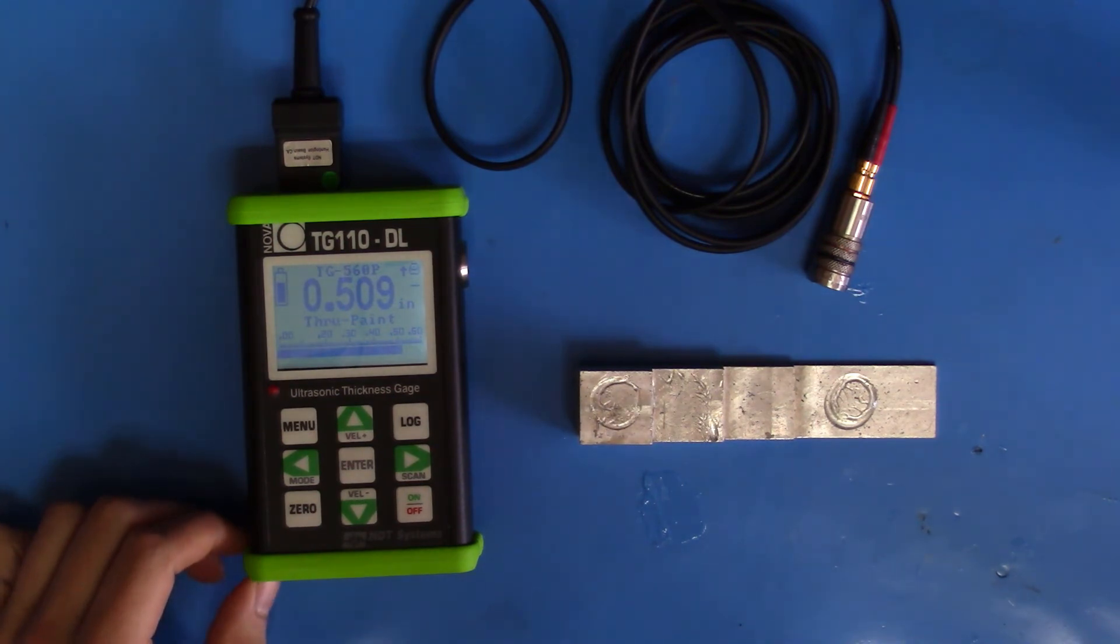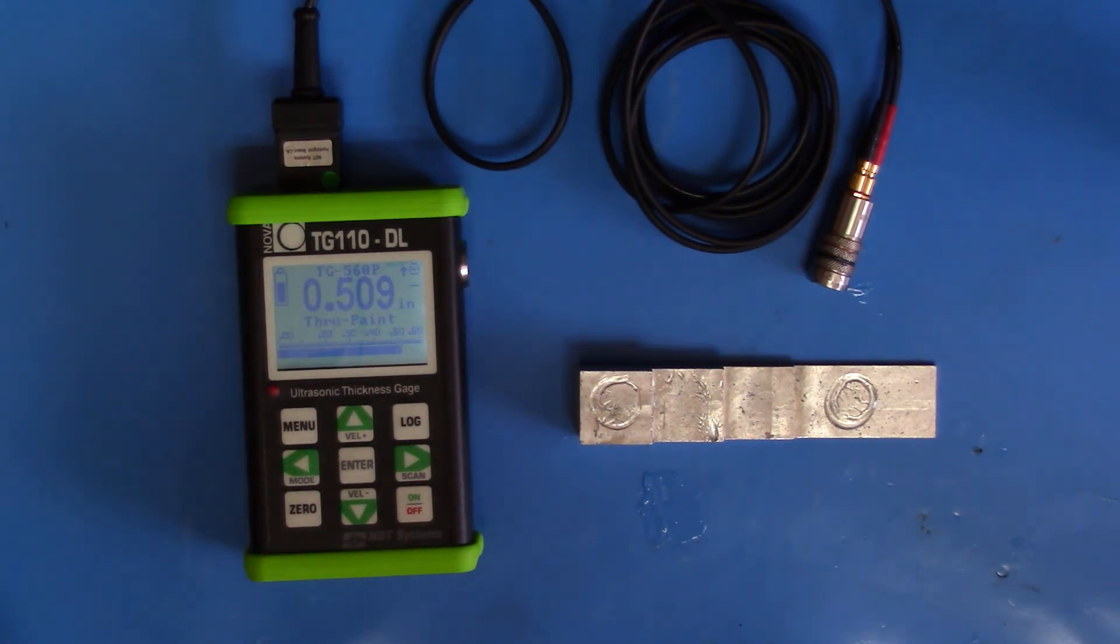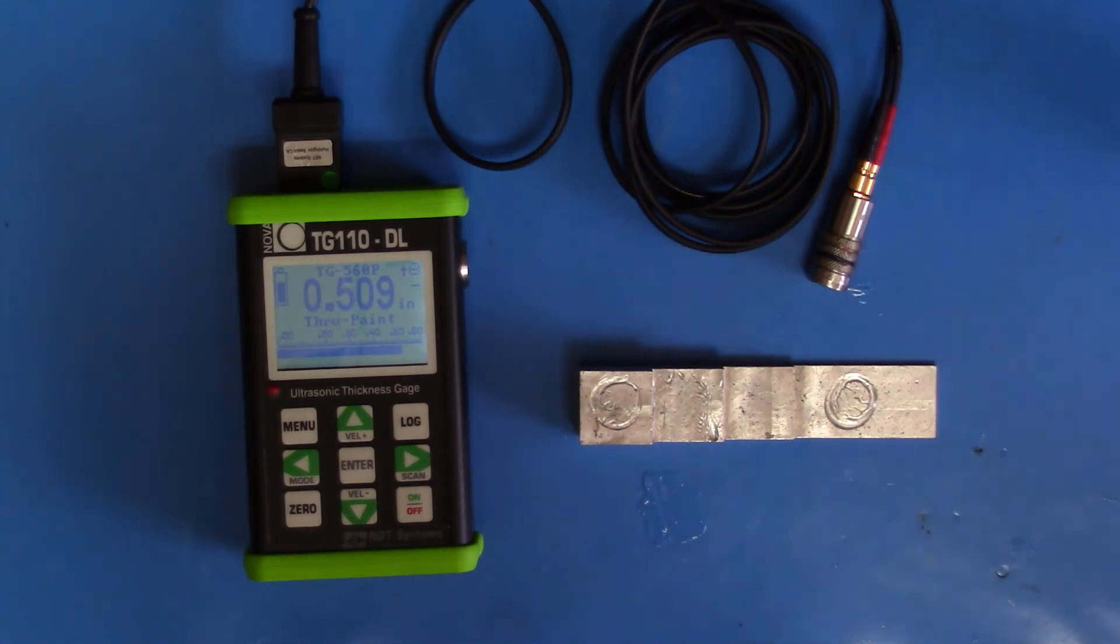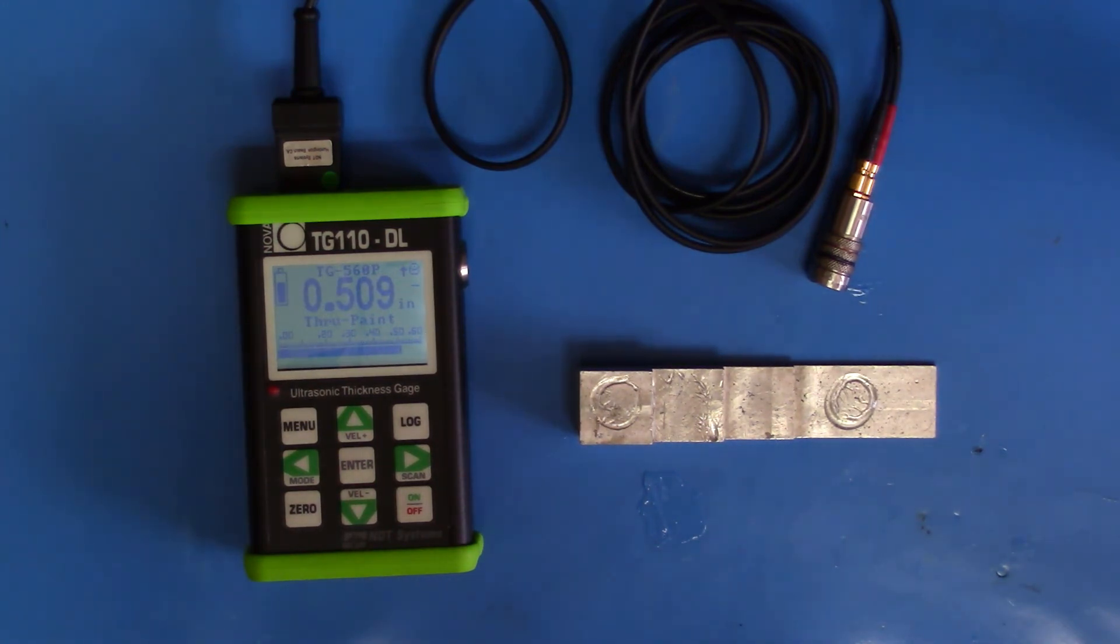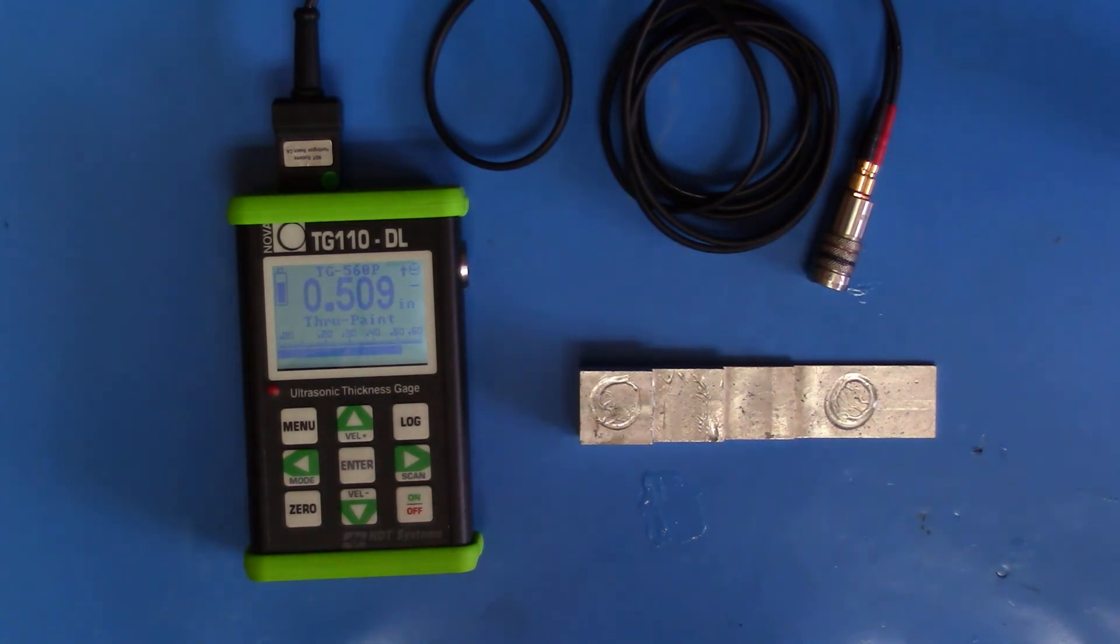One limitation you'll run into is your thickness range. Because it uses a delay line, there's a maximum thickness in steel of 3 inches. And because the software is excluding pulses near the interface, your minimum thickness range will be around 0.1 inches in steel.